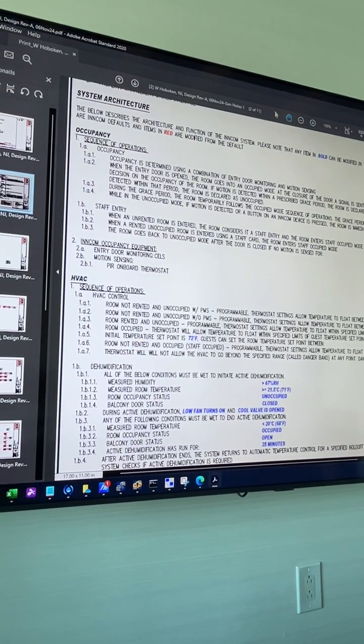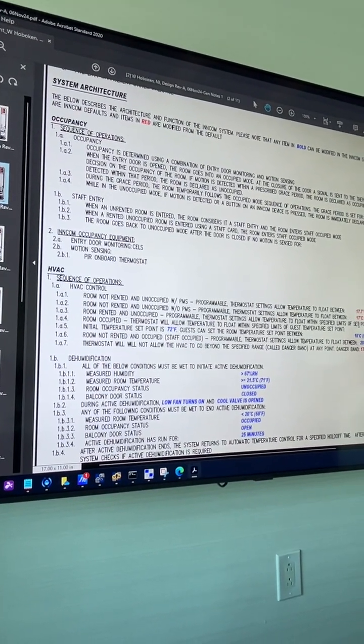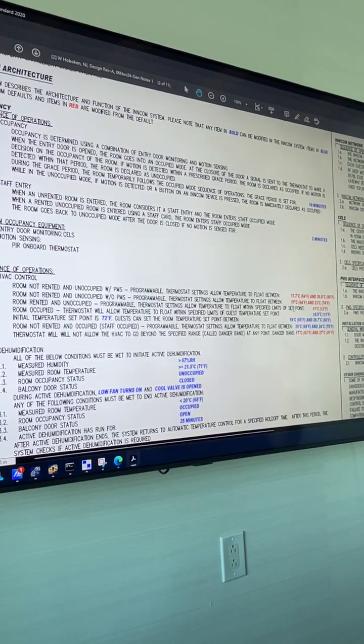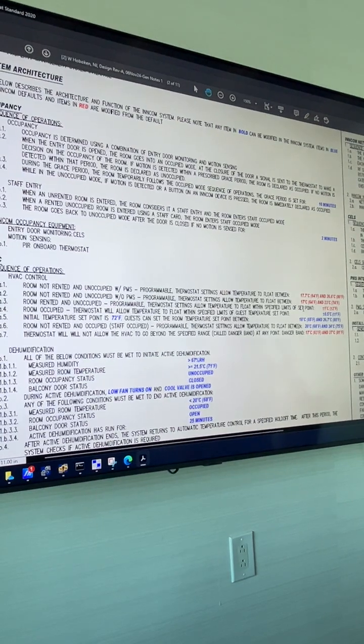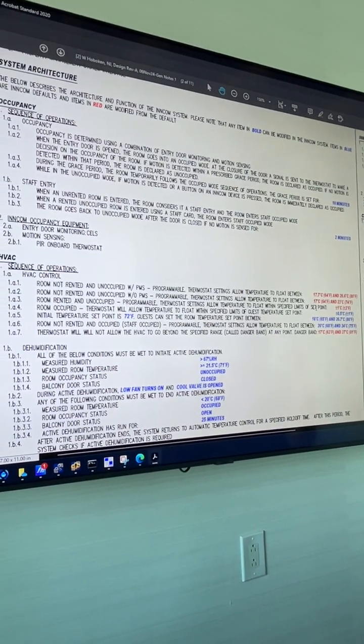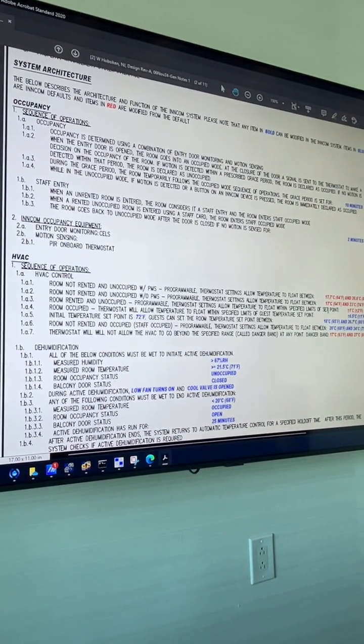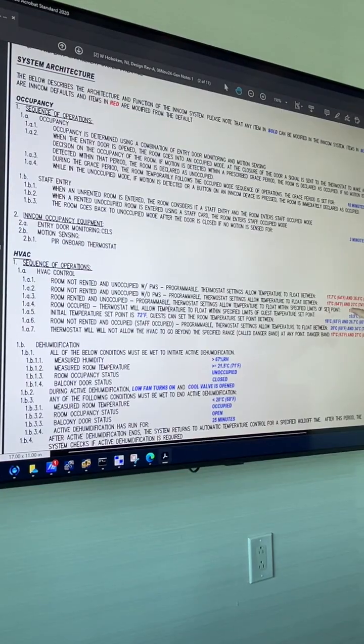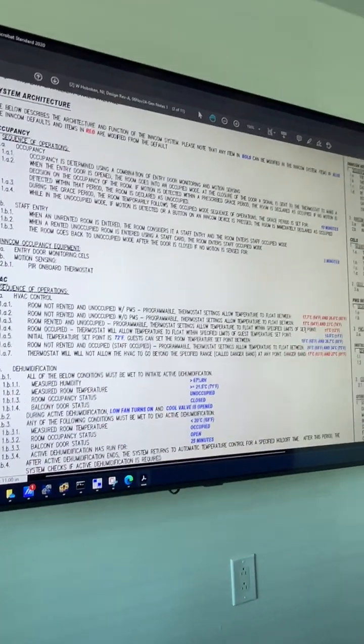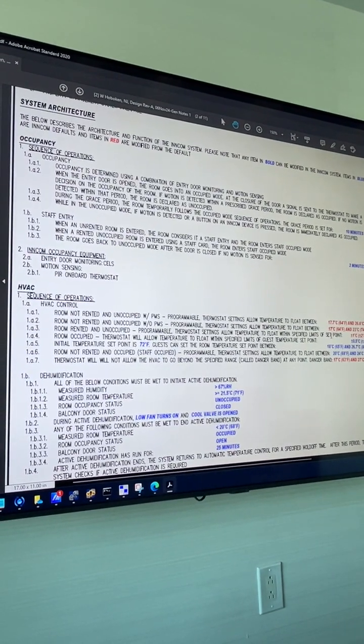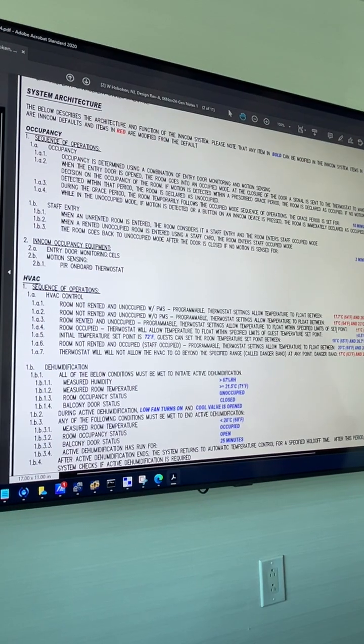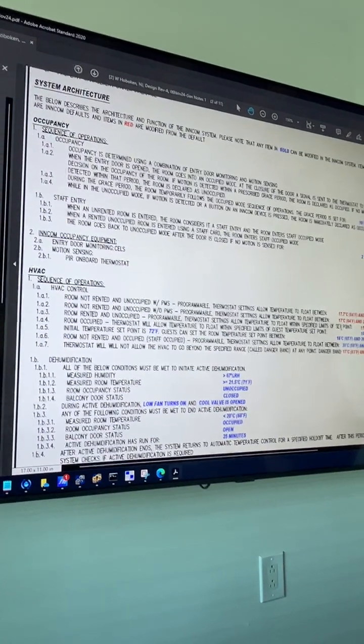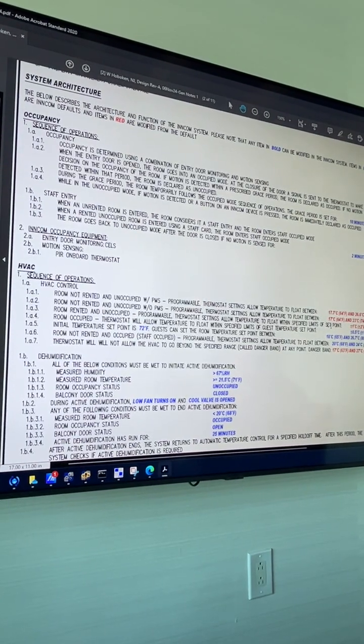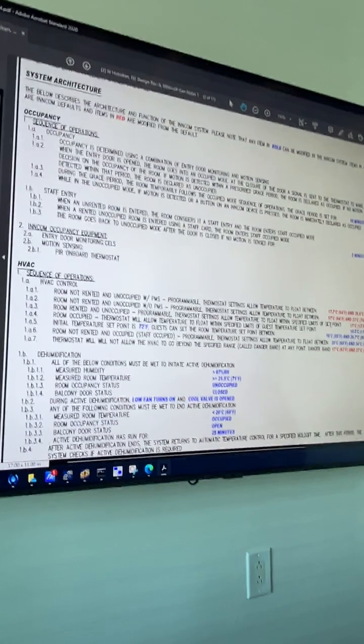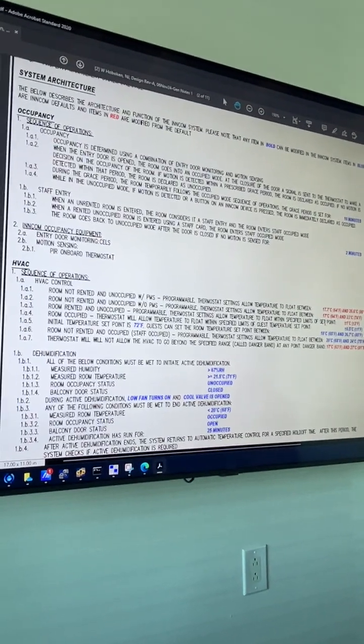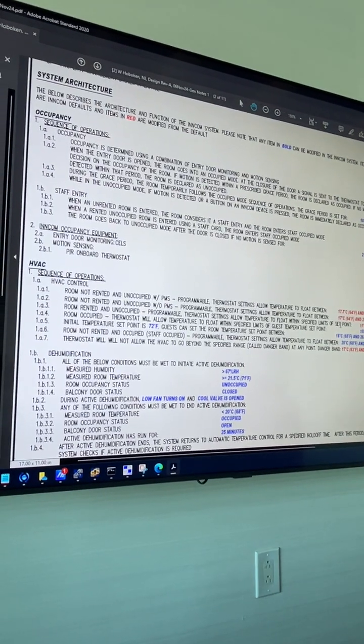Once the property management system is live, a room that's not rented and unoccupied can drift between 64 and 80 degrees. So it can get as cool as 64, as warm as 80 before kicking in the cooling or heat. Okay. Right now, since the property management system isn't connected, it's 64 to 74 is the band for a room that's considered unrented, unoccupied. That unrented is going to be if the room hasn't been entered in a long amount of time, since we're not actually receiving the messages from the property management system at this time. And that's just for the sake of the video. That's our Lightspeed, knowing that someone's checked into the room. Yeah, if I'm saying PMS, I'm referring to Lightspeed.